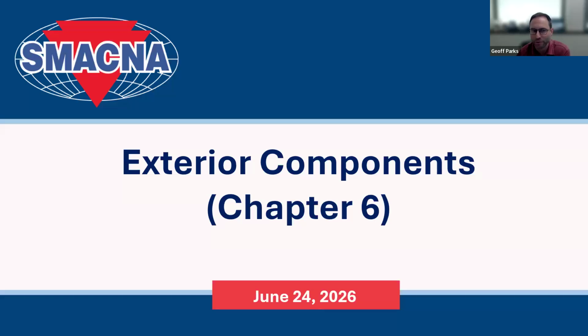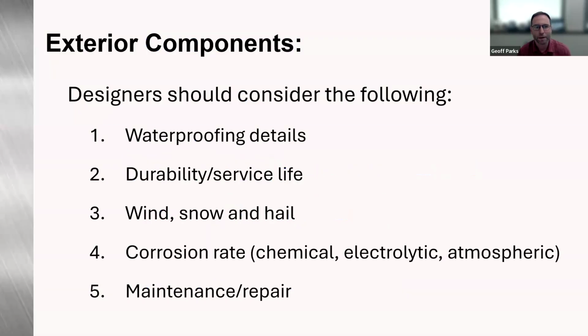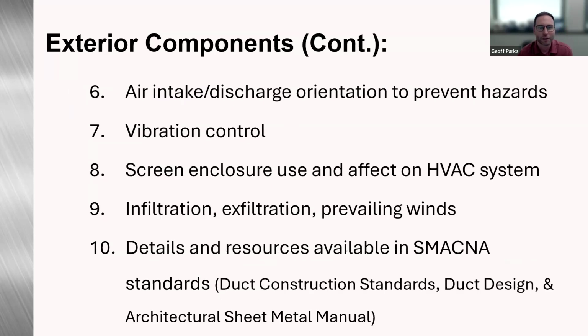So exterior components, this is Chapter 6 of the HVAC Duct Construction Standards. A couple of things to note. Designers should consider the following when designing for exterior components, whether that be ductwork, equipment, and so forth. Number one, waterproofing details. Two, durability and service life. Wind, snow, hail, and exterior loads that are going to be put on that ductwork. Corrosion: chemical, electrolytic, atmospheric. That one trips me up all the time. Maintenance and repair. Air intake and discharge orientation to prevent hazards. Vibration control. Any screen enclosures that are used that may affect the HVAC system. Infiltration, exfiltration, and prevailing winds.